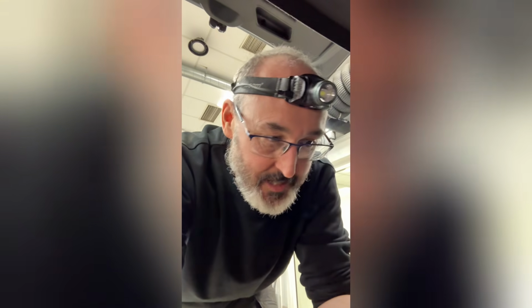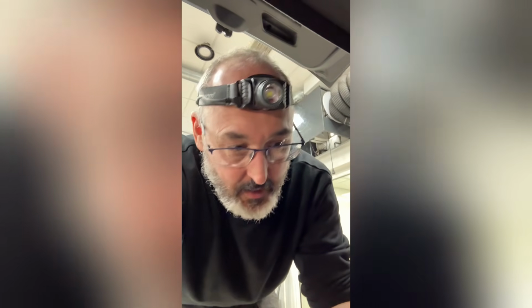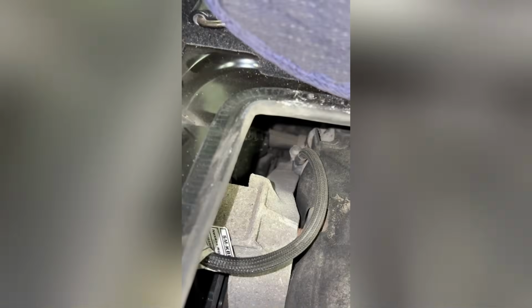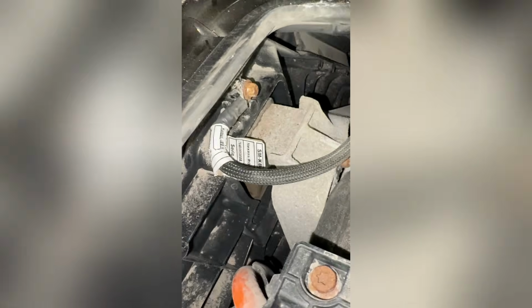So I need to clean this, and I'm going to explain exactly what we're going to test. Down there is the equipotential bonding point, the other part on that screw. What I'm going to aim to do is go just at the side of the screw onto that spade terminal, and then we need to get as close to zero as possible - we don't want a mega ohm value.